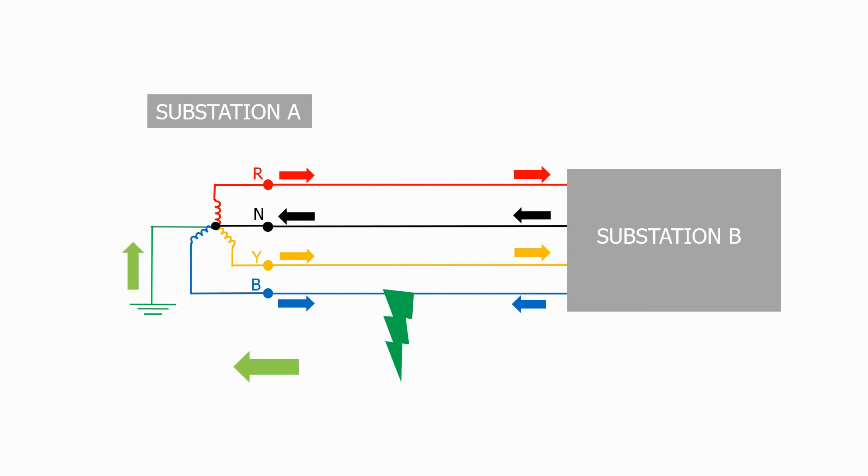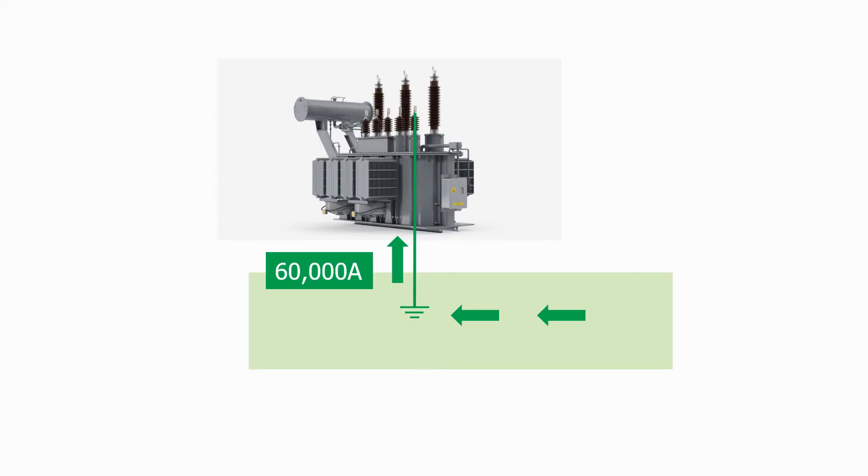In transmission substations where we can have a fault current of 60,000 amps, this voltage rise can be hundreds of volts. This voltage is called ground potential rise and all of the ground beneath the substation will rise to a similar high level. This can be extremely hazardous for anyone working inside the substation as the magnitude of the voltage at their feet can be different to the voltage found in the metallic objects that they may be touching.